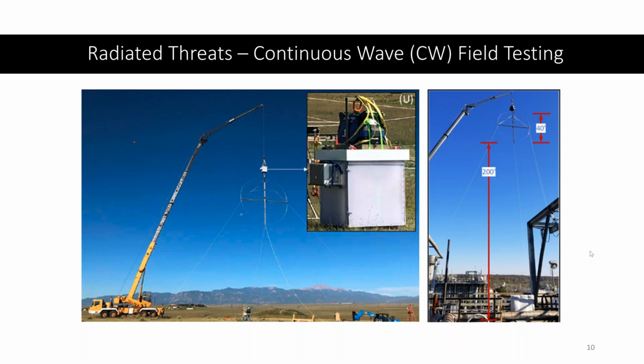But we did find some very important findings. This continuous wave field is very low energy, only a hundredth of a volt to 1 volt per meter, and we still found that energy was getting into the control cables, and the distributed control system wasn't damaged, but it was noticing that there were problems and alarms were sounding.